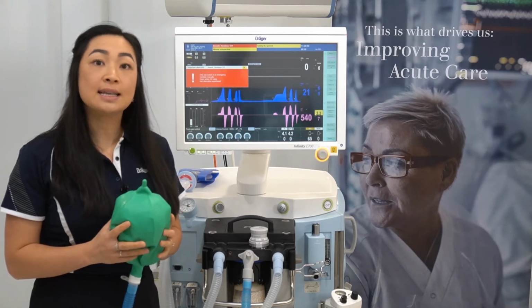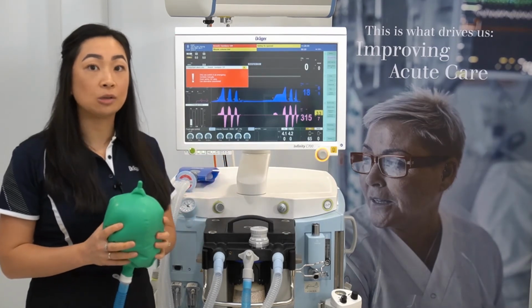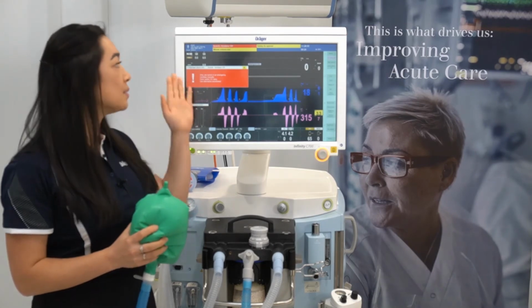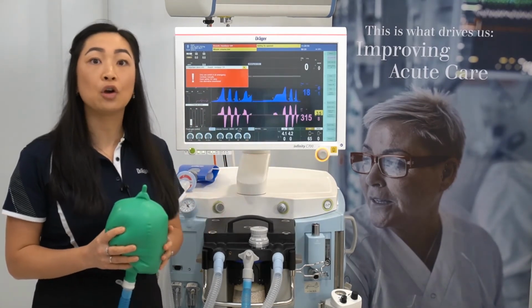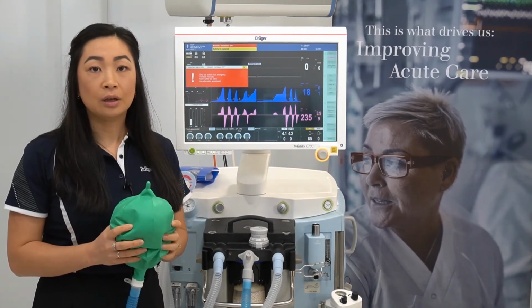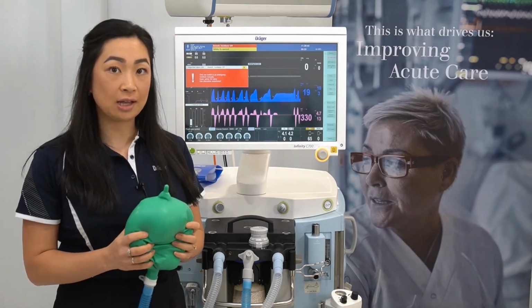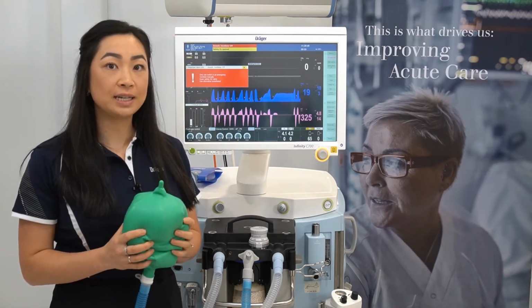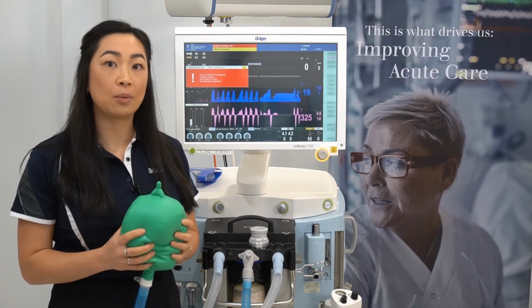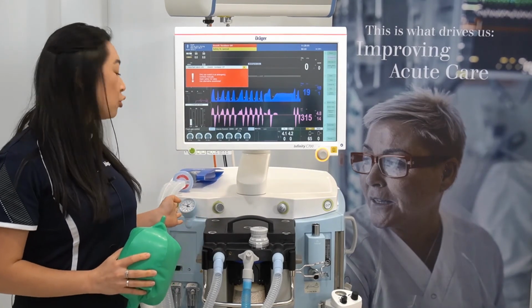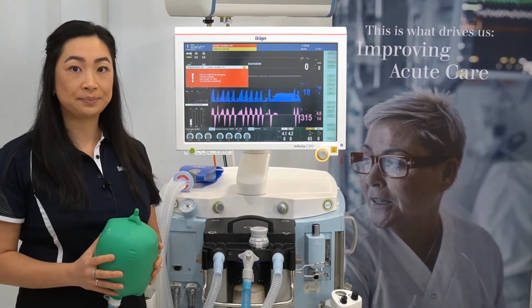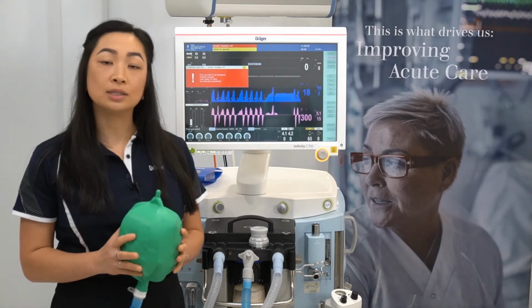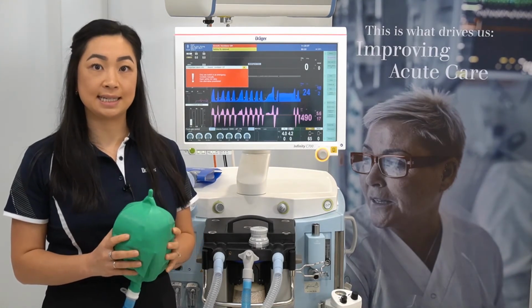For users that still have their screen display available, you can verify your gas measurements, pressure and flow on the screen. If the screen is unavailable, you can verify manual ventilation and the patient's airway pressures against the manual pressure gauge on the device. Then, contact your technical service representative.